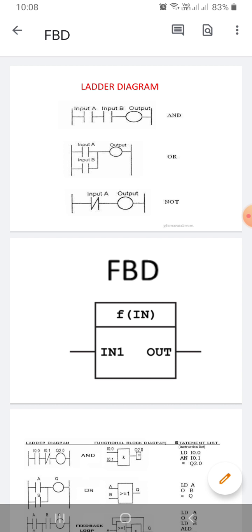The main feature of the ladder diagram is that the power always flows from left to right. The output on the right side cannot be connected directly with the left side. A contact cannot be placed on the right of the output. Each rung contains at least one output, and each output can be used only once in the program.